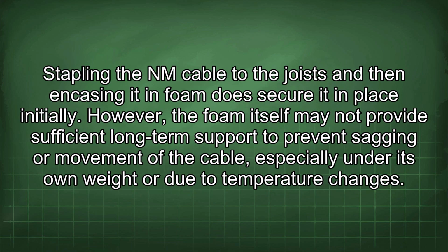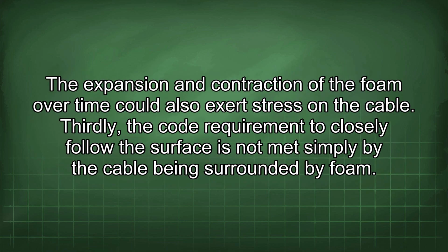Secondly, the method of attachment is a key consideration. Stapling the NM cable to the joist and then encasing it in foam does secure it in place initially. However, the foam itself may not provide sufficient long-term support to prevent sagging or movement of the cable, especially under its own weight or due to temperature changes. The expansion and contraction of the foam over time could also exert stress on the cable.